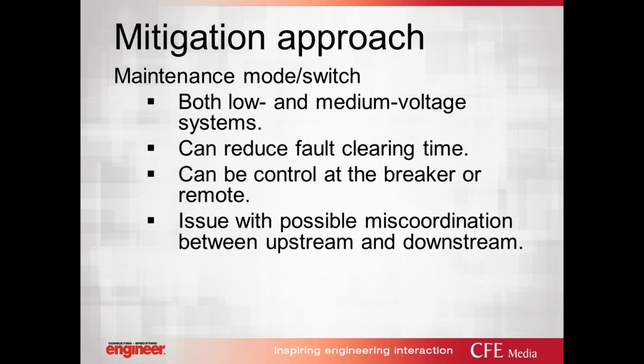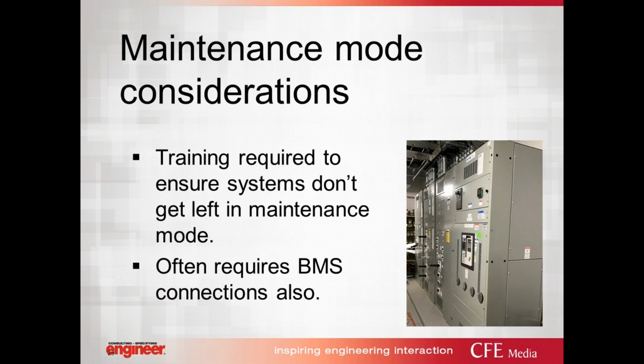The next approach, maintenance, I'm sure most of you may be utilizing that before. This can be in both LV and medium voltage system. The intention here is to reduce the fault clearing time. It can be used at the control at the breaker or remote. Again, one of the issue with this approach may be miscoordination, because during this time, you're not going to have a coordinated system. Therefore, you need to be careful during this time, having a procedure and approach in place to make sure this will not causing any issue in the system. At this point, I will pass it to Tracy to continue my discussion with the sample of their facility and from that.